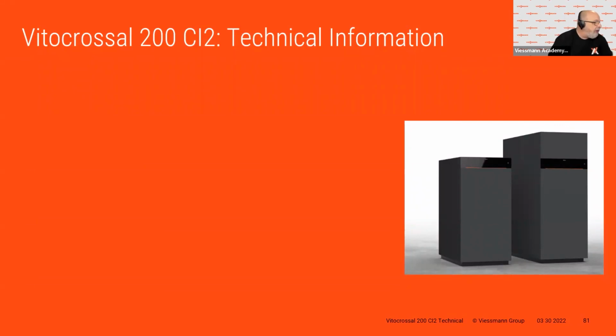Be careful. Would the header supply water temperature set point still be maintained if the lead cascade boiler is offline? If the lead cascade boiler is offline, the lag boilers will continue to do whatever their last set point was. If the lead boiler is being serviced, it still has power, the control's still working, but it won't run, let's say. It's off on a failure, like flame failure or low water cutoff or whatever it is. The cascade continues to function and it will operate the lag boilers to that set point that's going to change by whatever happens. But if the lead boiler is physically powered down or doesn't have any ability to tell the boilers what to do, the lag boilers will continue to do what they were told to do last as far as the set point goes.